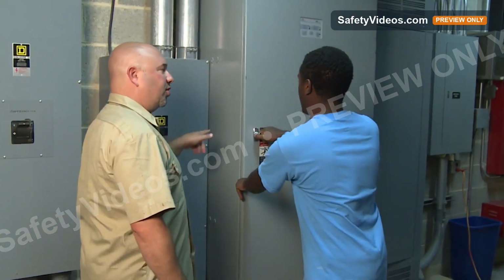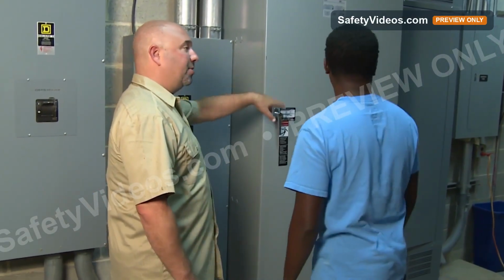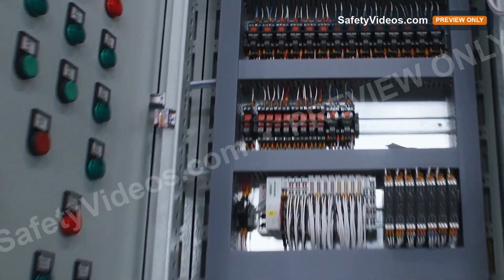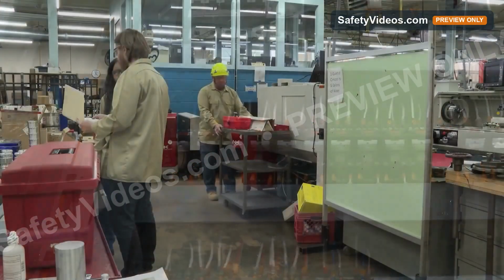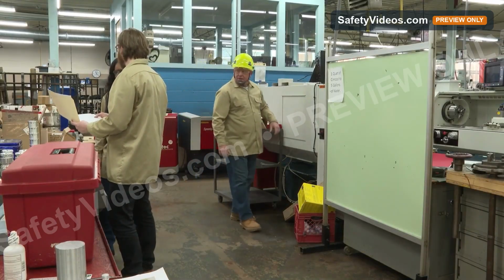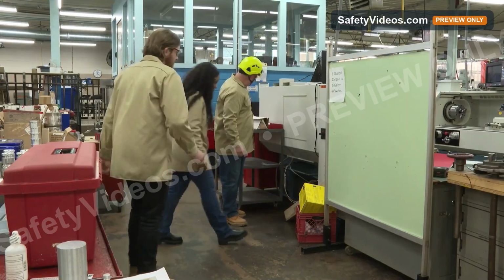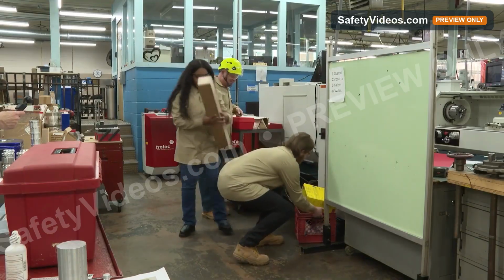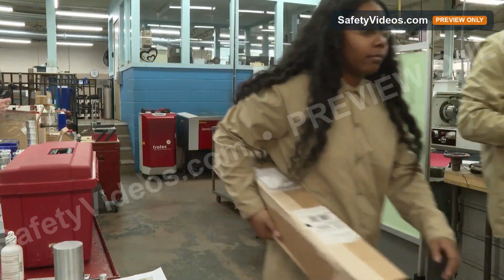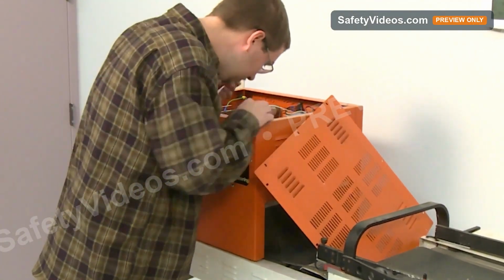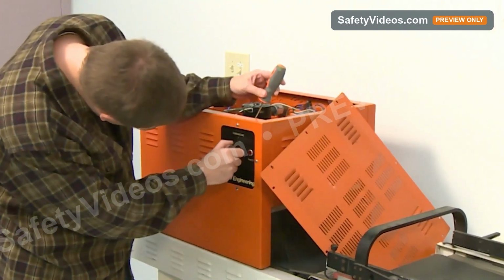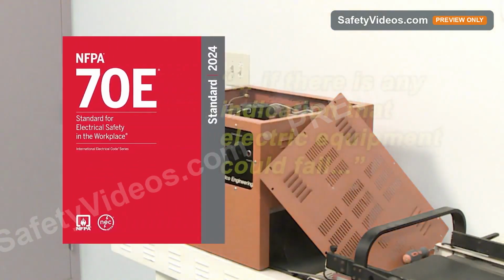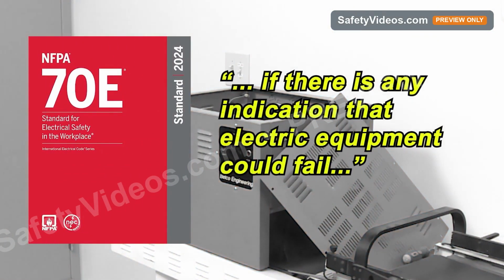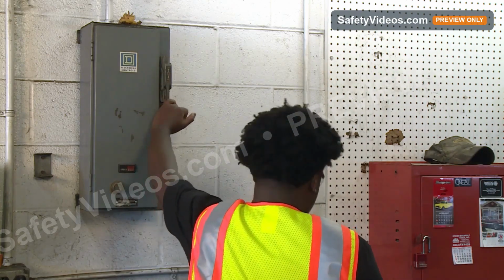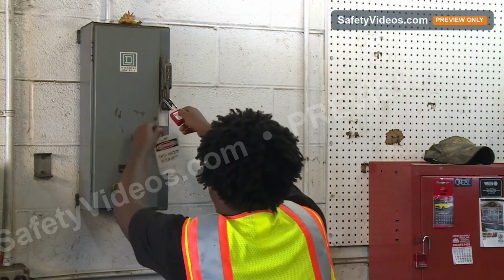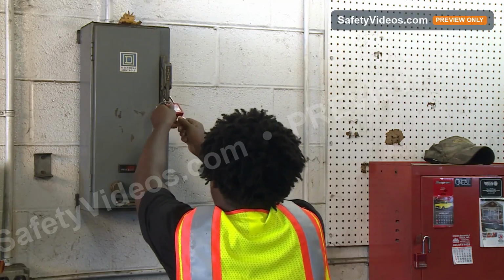And any doors or hinged panels on equipment that you're working with must be secured. Otherwise, they could swing open, exposing you to energized electrical conductors or circuits. If your work area is overcrowded or messy, it could prevent you from having clear access to the equipment or to escape passages. So before you start any job, always make sure the surrounding area is neat and clean. But in some cases, despite all of these precautions, the equipment that you're working on could fail on its own. So NFPA 70E advises that if there is any indication that electric equipment could fail, it should be de-energized immediately. If this does happen, you should not re-energize the equipment until the cause of the failure has been identified and repaired.